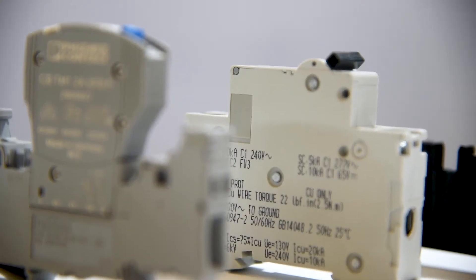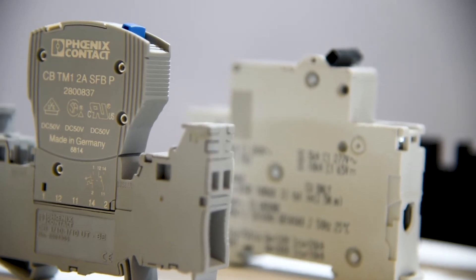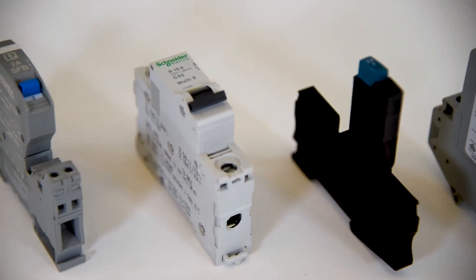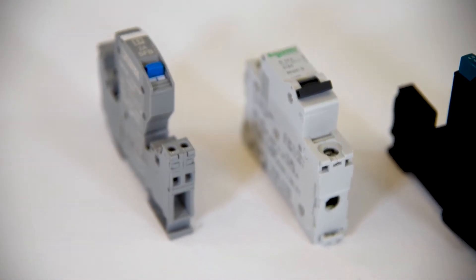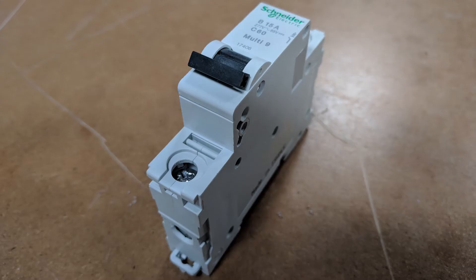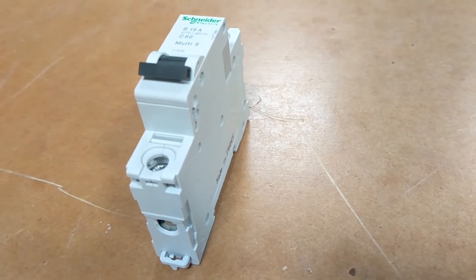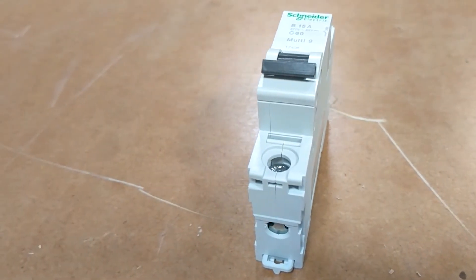One of the first things we look at in the hardware selection process for power distribution is our main panel breaker. We want to make sure this breaker is at the very least a branch circuit breaker — a breaker that protects multiple devices. Everything downstream of this main panel breaker is what it's intended to protect. This is known as a UL 489 listed breaker. If you intend to list your panel with UL, you have to use a UL 489 listed breaker, and branch circuit breakers typically fall under UL 489. We try to use these UL 489 listed breakers in all of our main panel breaker applications.